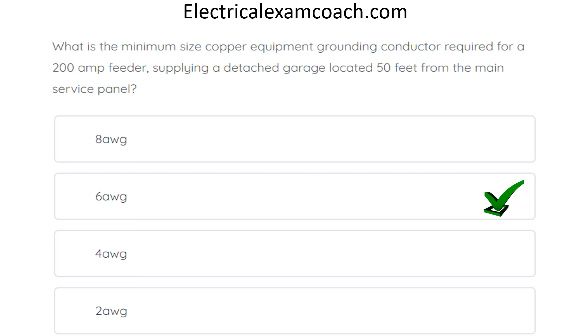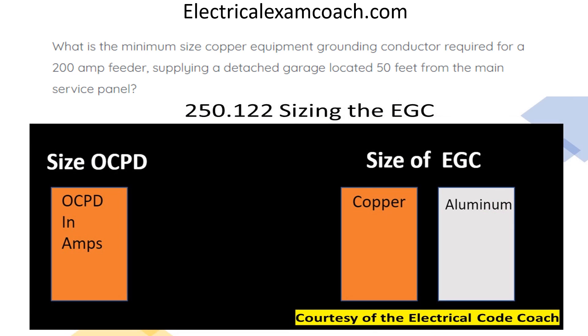The correct answer is 6-gauge wire. It doesn't matter if it's 50 or 100 feet from the panel — the test makers love to include distances to throw you off. An equipment grounding conductor is required, and it must be sized per table 250.122. We start on the left-hand side and select our overcurrent protective device rating, which is 200 amps. Then we cross over to the copper column and select number 6.